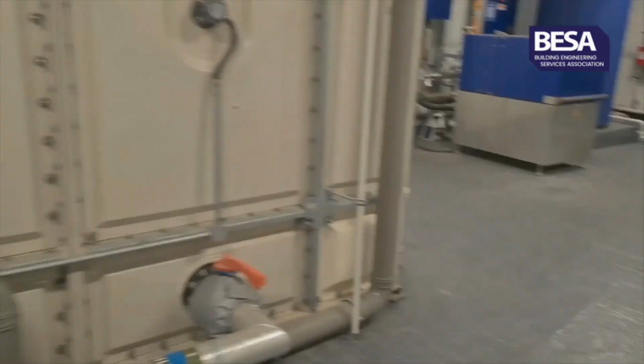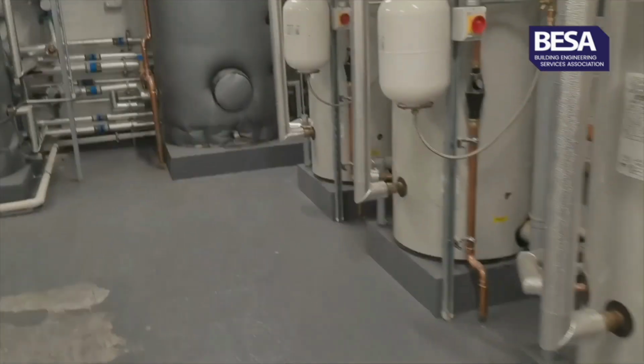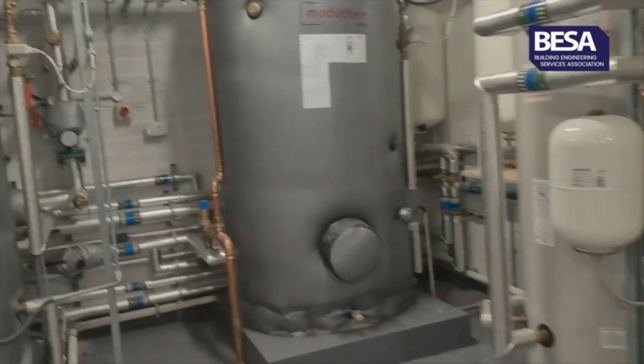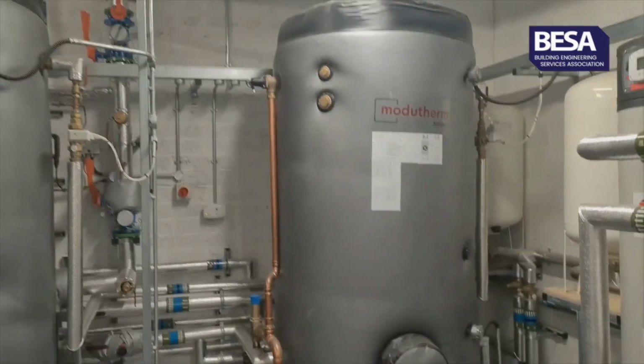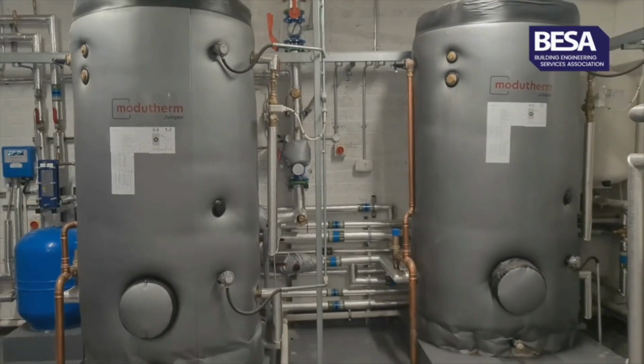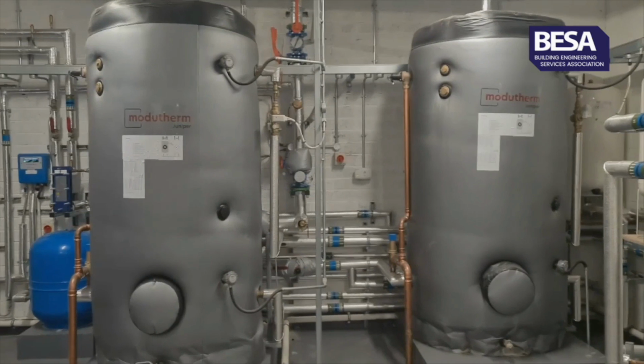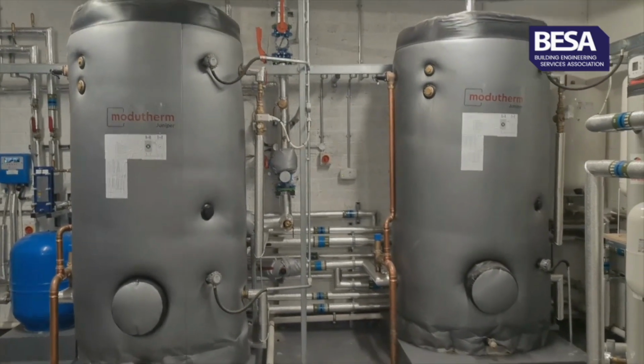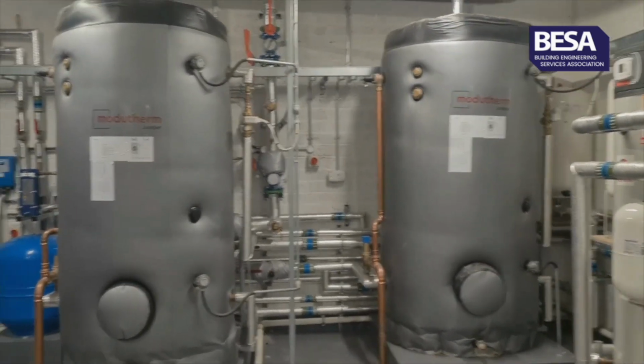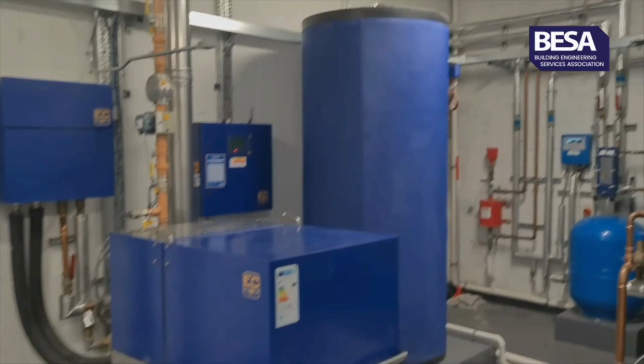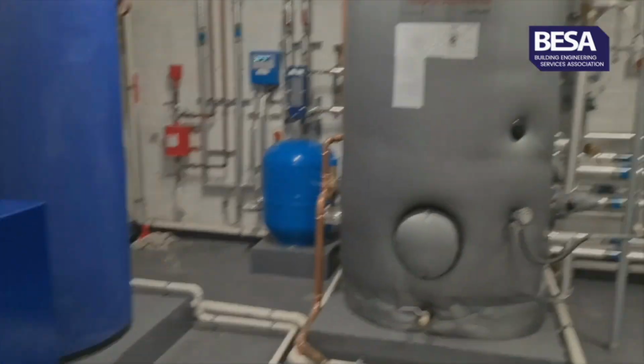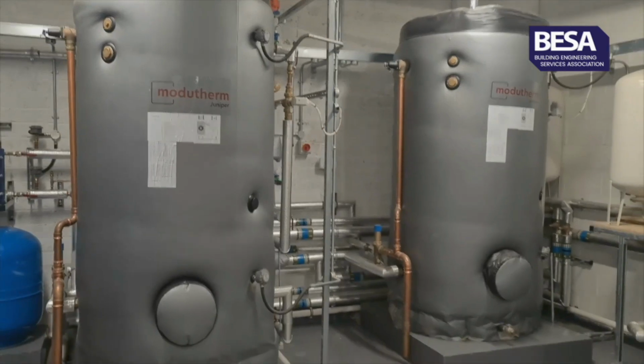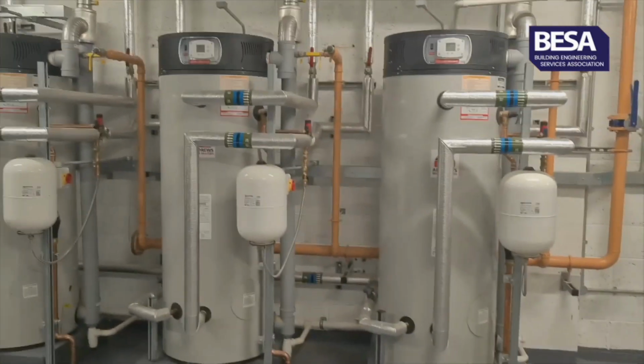So going back to the hot water, as mentioned earlier, we've got gas-fired water heaters and CHP. We've then got these 2 big buffer vessels. This is the hot water storage, so it's quite a high demand here for hot water. The principle is the CHP will operate first, and then as required, these cylinders will be topped up by the gas-fired water heaters.